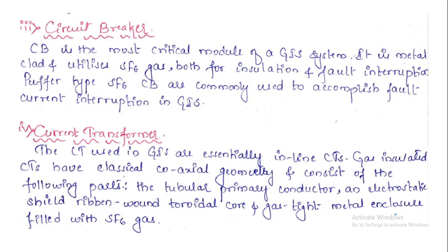It consists of a movable cylinder where SF6 gas is filled. As and when the moving contact starts separating, this moving cylinder also starts moving, so that the SF6 gas gets compressed, and through the nozzle that SF6 gas is released between the two contacts. So the arc interruption process begins. This is about the circuit breaker, where SF6 gas is used as an arc quenching medium.